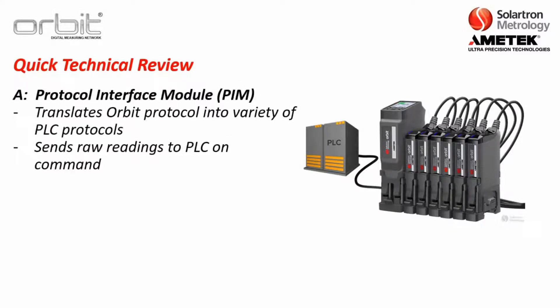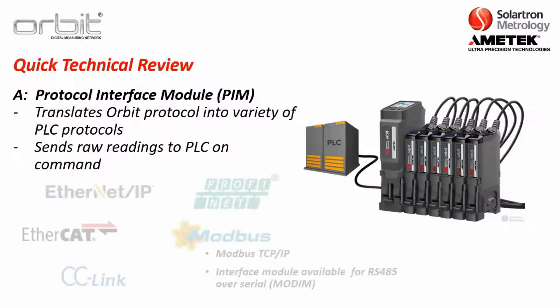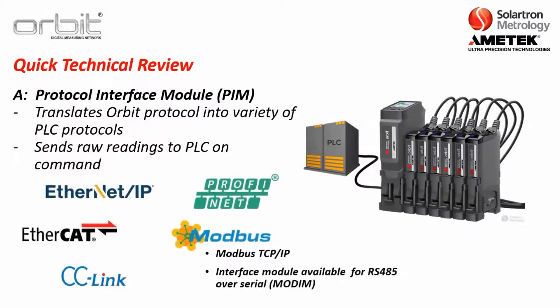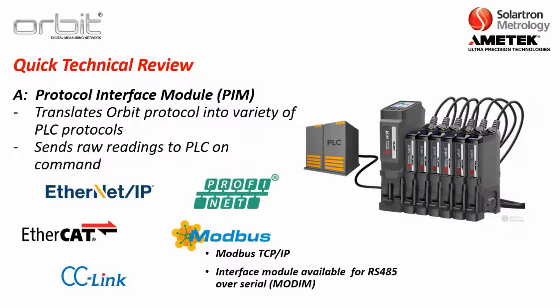So before we get started how about just a quick technical review. First the Protocol Interface Module, what it in essence does is basically translate the Orbit Protocol into a variety of PLC protocols. And then it will just send the raw readings from these sensors to the PLC on command. And we actually have several different types of PIMs. The PIM for Ethernet IP, one for Profinet, one for EtherCAT, one for CC-Link, which should be available in late 2021, as well as a PIM for Modbus over TCP IP.